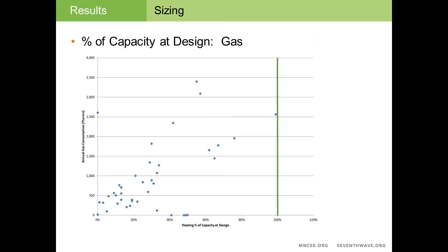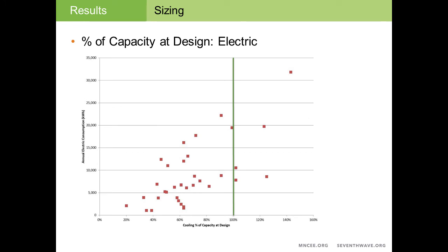These are the results of the capacity at design conditions for the gas data. This is the heating percentage at capacity or at design for the gas use. And if you drop all these points down onto the x-axis, you will see that they all reside somewhere below 40%. The majority of them are landing there. We decided to plot the annual energy use against the heating percent of capacity to give you a good indication. And there's no surprise that the closer the unit is to design, the more energy it uses. If we look at the electric side, we're closer to design capacity.